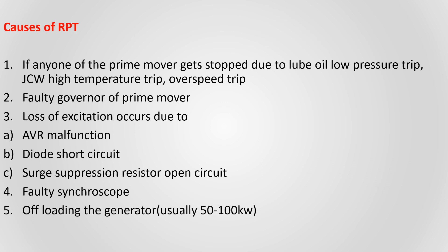Offloading the generator is usually done at 50 to 100 kilowatt. During idle condition, fuel is still being admitted to the engine — that mechanical power of around 100 kilowatt is used to counter the friction and windage losses. If you offload at 0 kilowatt, reverse power flow will occur. That's why we offload the generator at 50 to 100 kilowatt.